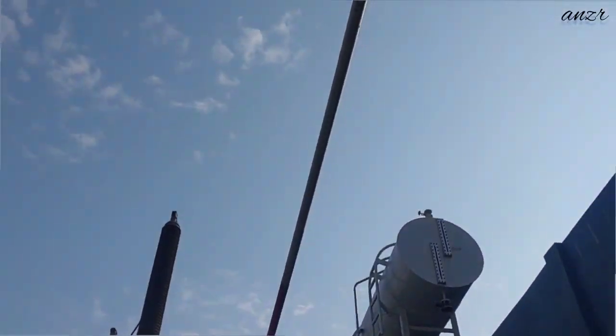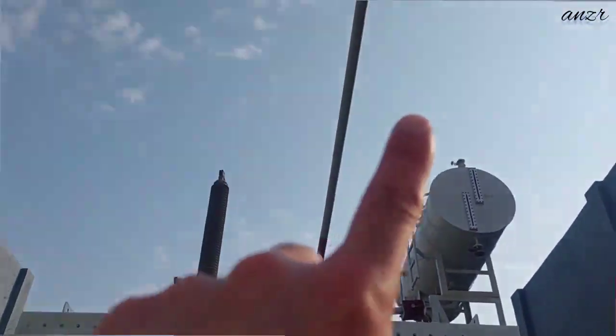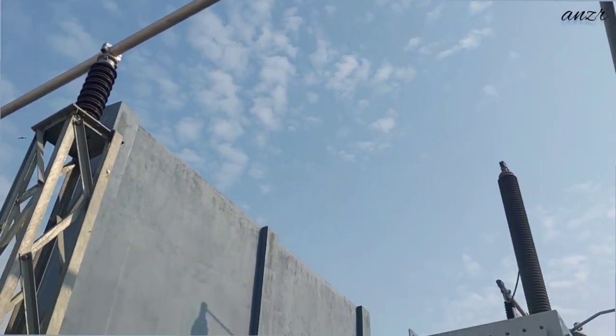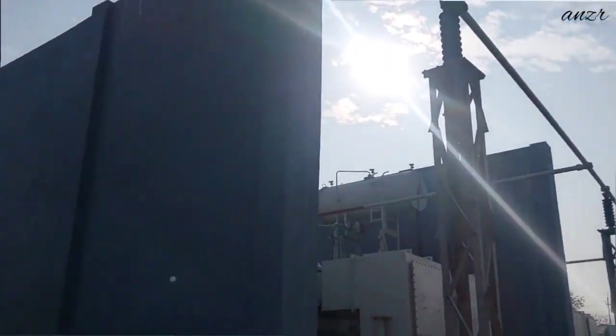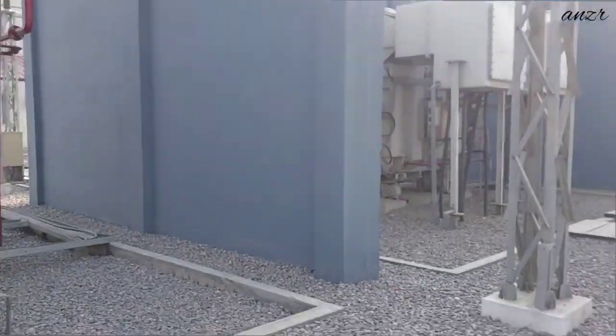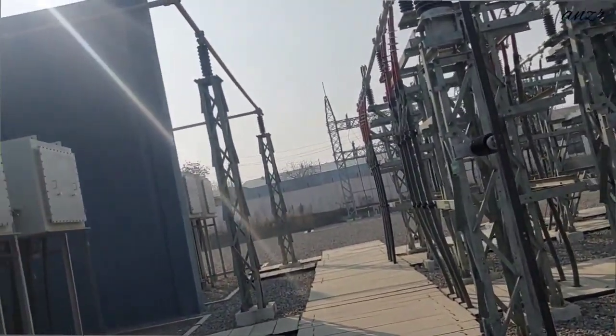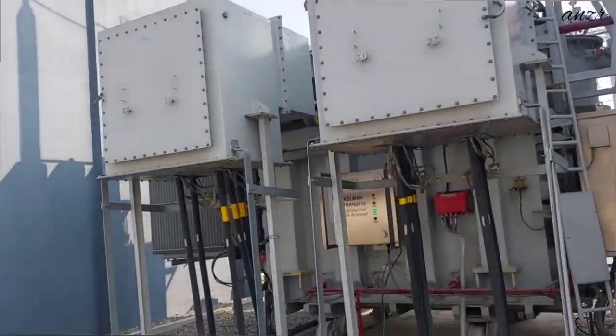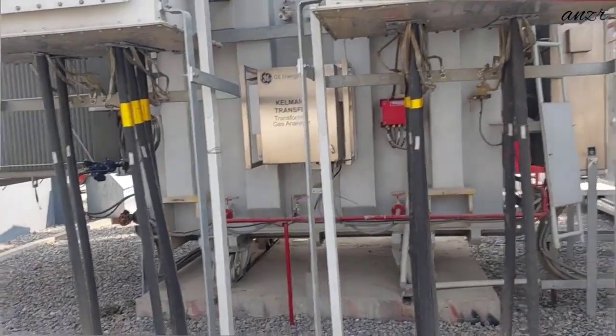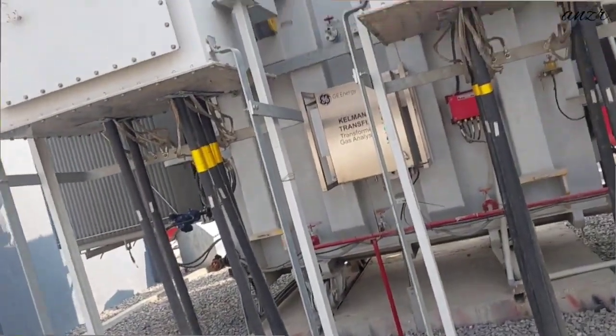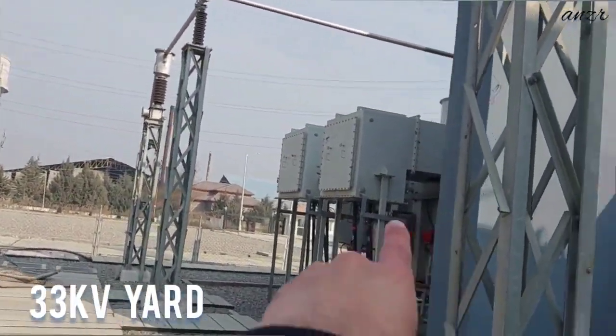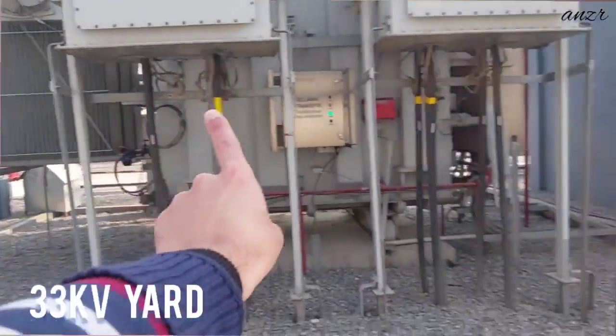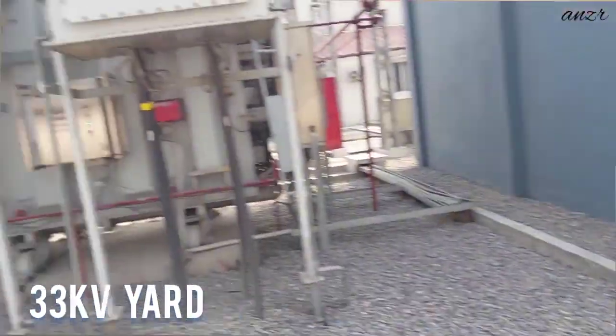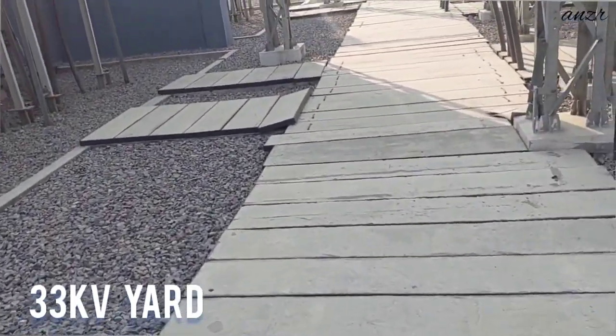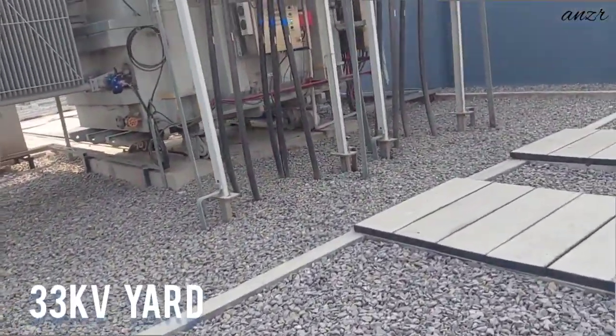So here you can see this transformer, the secondary side. So it charges this primary bus here, 33 kV bus. So it is charged by these transformers. So after that, let me show you this. This is the secondary side. You can see how many lines are coming out from this transformer. So this is separately used. This is the red phase, this is the yellow phase, and that is the blue phase. So 33 kV lines are coming out of these three transformers, 3-phase 33 kV from all of these three transformers.